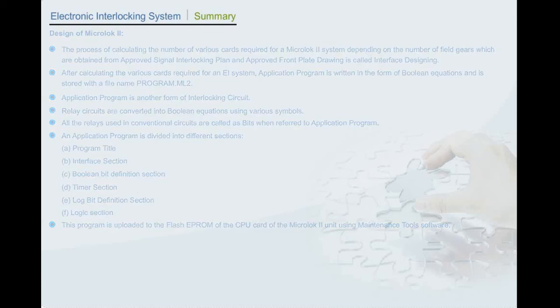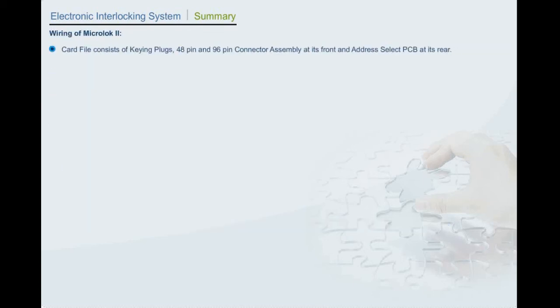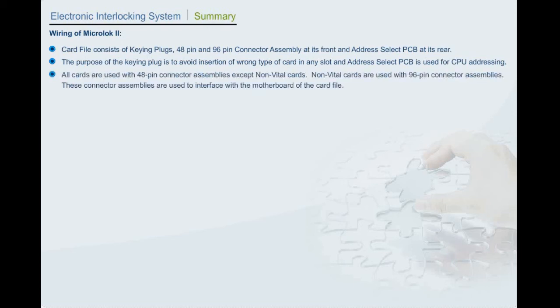using Maintenance Tools software. Wiring of Microlok II. The card file consists of keying plugs and 48-pin and 96-pin connector assemblies at its front, and an address select PCB at its rear. The purpose of the keying plug is to avoid insertion of the wrong type of card in any slot, and the address select PCB is used for CPU addressing. All cards are used with 48-pin connector assemblies except non-vital cards. Non-vital cards are used with 96-pin connector assemblies. These connector assemblies are used to interface with the motherboard of the card file.